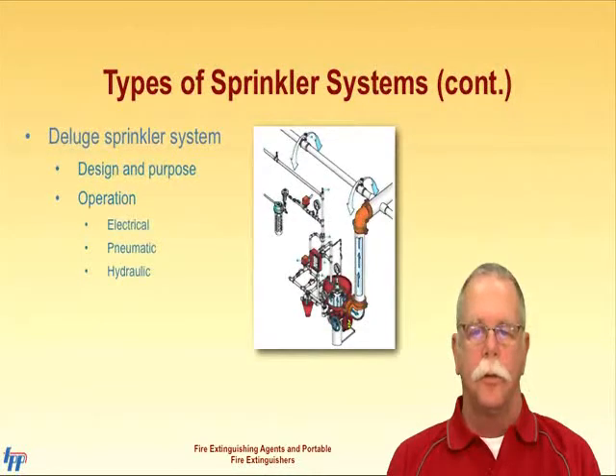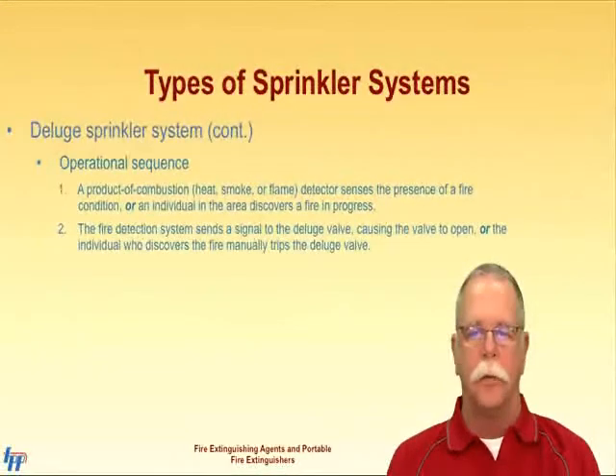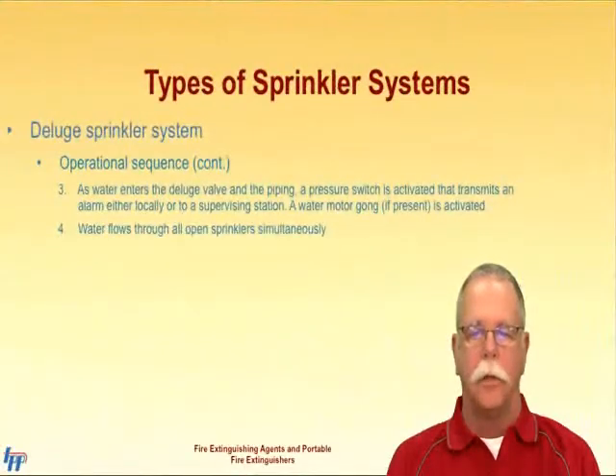A deluge system is similar to a dry pipe system in that there is no water in the piping before activation. However, in a deluge system, all the heads are open. There is no heat detecting device in any of the heads. A fire is detected by a detection device, such as a smoke or flame detector, thereby activating the sprinkler system. These systems are designed to deliver a high volume of water to the protected area. They can be found in extra hazard areas such as aircraft hangars, woodworking shops, or ammunition storage. They also may be found in shopping malls where a division of occupancy is needed that can't be provided by firewalls.